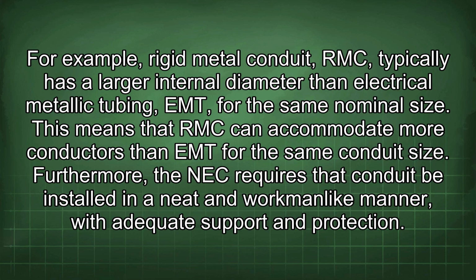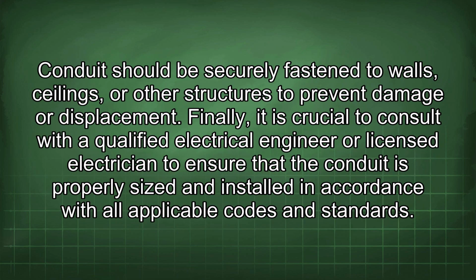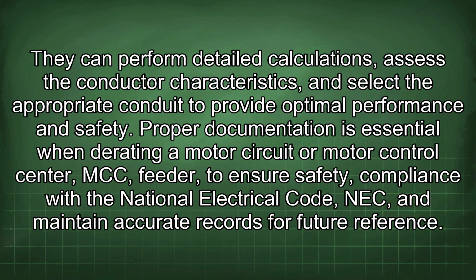Furthermore, the NEC requires that conduit be installed in a neat and workmanlike manner, with adequate support and protection. Conduit should be securely fastened to walls, ceilings, or other structures to prevent damage or displacement. Finally, it is crucial to consult with a qualified electrical engineer or licensed electrician to ensure that the conduit is properly sized and installed in accordance with all applicable codes and standards. They can perform detailed calculations, assess the conductor characteristics, and select the appropriate conduit to provide optimal performance and safety.